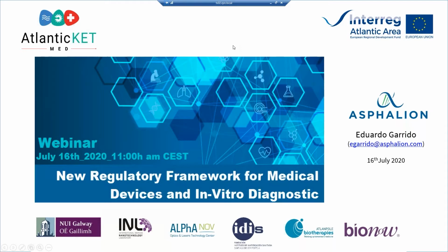Well, sorry, I cannot see the person that has asked this question. Could you clarify, when you say using off-the-shelf components already certified, what do you mean here? Because you say it's required that the medical device integrating such a component is tested. Yes, in principle, it's going to have to be tested, even if the component is already certified. I guess you're not asking about the testing of ancillary medicinal substances. Can you clarify, please?